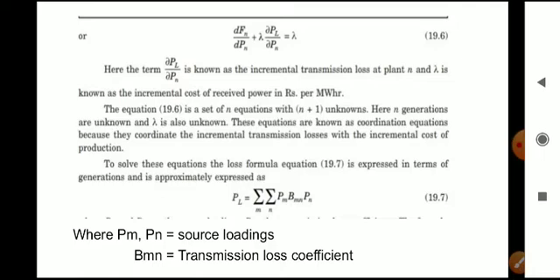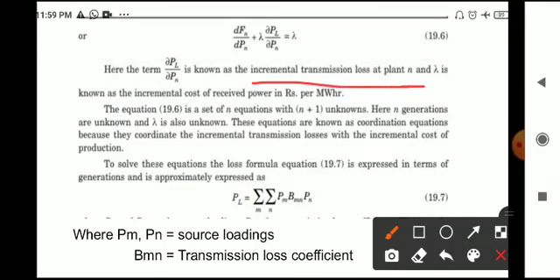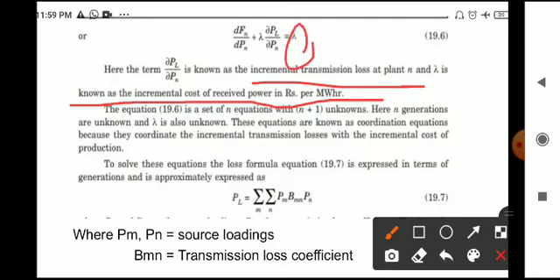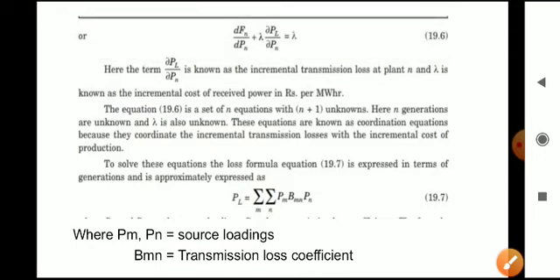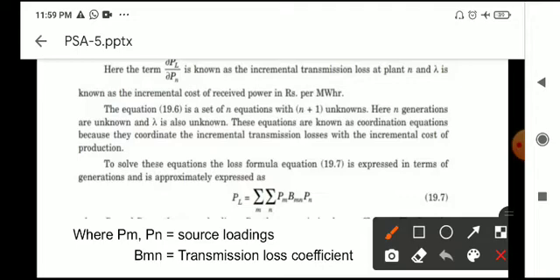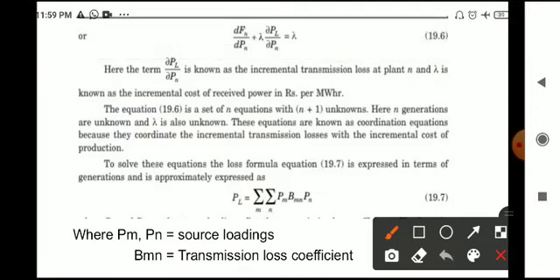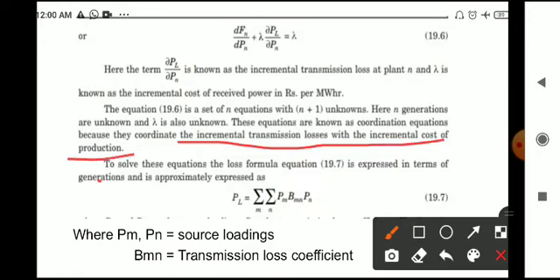Here dPL/dPn is known as the incremental transmission loss at plant n, and lambda is known as the incremental cost of received power in rupees per megawatt-hour. This set of n equations with n+1 unknowns — n generations and lambda — are known as coordination equations, because they coordinate the incremental transmission losses with the incremental cost of production.